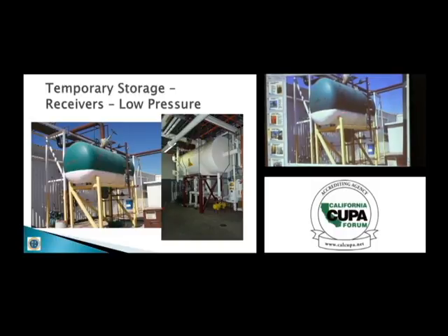Well, we see the apparent level in this vessel. Now, I know you're already concerned, okay, what about this bucket? And I bet you're concerned about, well, apparently they're dumping that oil into here, and clearly it does not have an accumulation sticker, right? Oil waste and all that, and there's no secondary containment. But we've got here, you can see the level switch, and there is a red light. But do you see Casper tracks? No. If I got Casper here, but I don't have him there, I must have something else there, like a lot of oil. So the red light's not lit, but the apparent level is higher than the safety.